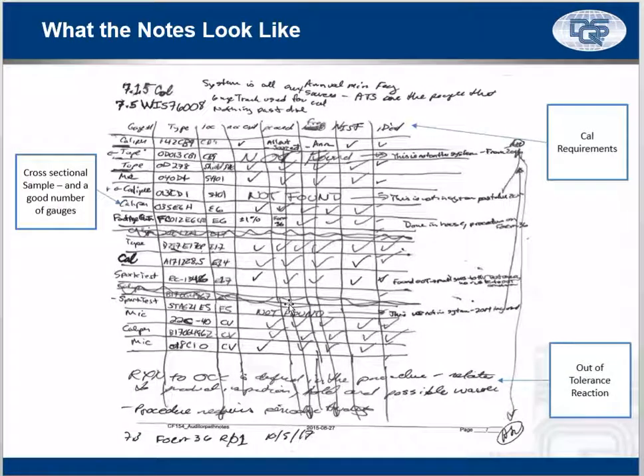Okay, so what do your notes look like? I, again, highly recommend the table. Now, this is from my notes, so you can see it's really messy because I'm not a good writer, and you can see, like, I said type here, but I actually put the gauge number, and I put the gauge type here. But what you really should be looking at is, what was I looking at? Here I got micrometer, I got calipers, I got a spark tester, I have a tape measure. I have a cross-section of the gauges. This particular company, that's basically the gauges they had. They didn't have much more than that.